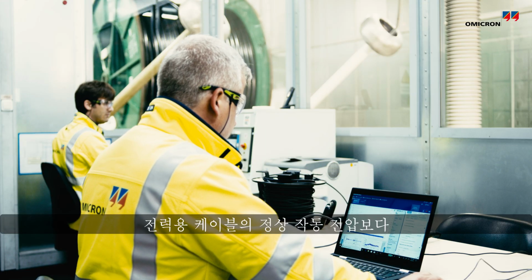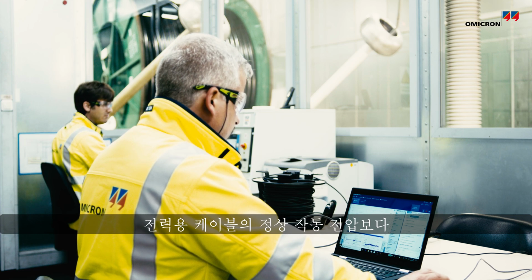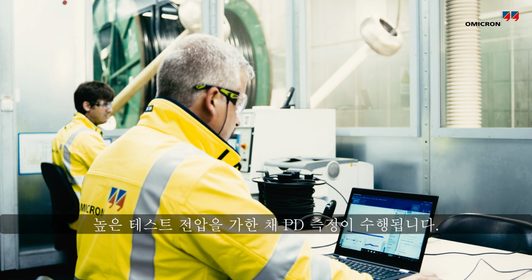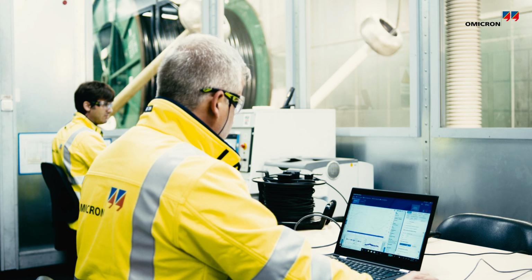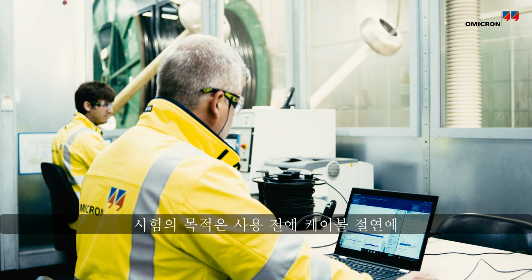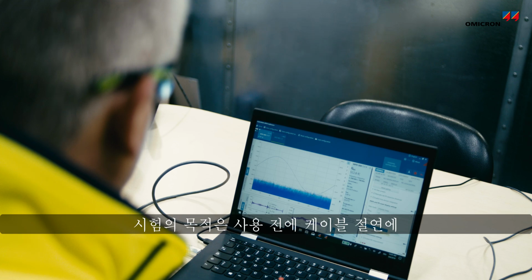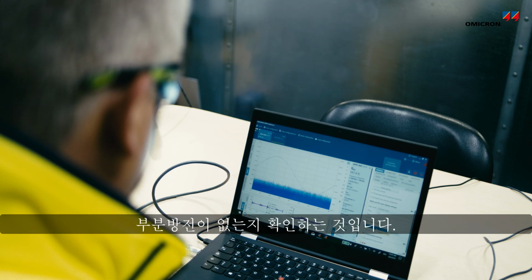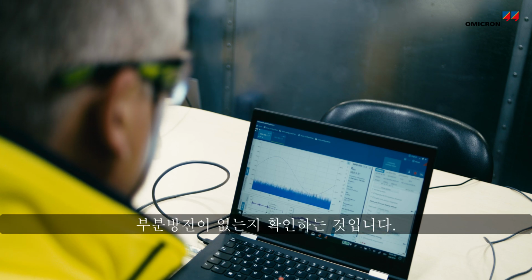A test voltage is applied that is higher than the normal operating voltage of the power cable, and the PD measurement is made. The goal of the test is to determine whether the cable insulation is free from partial discharge before it is released into service.